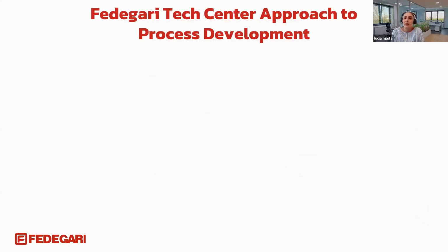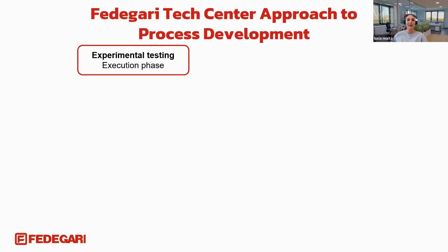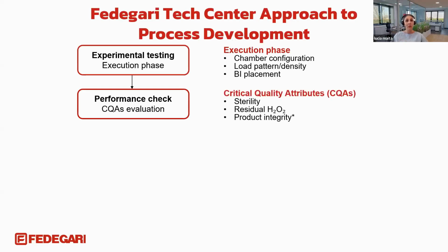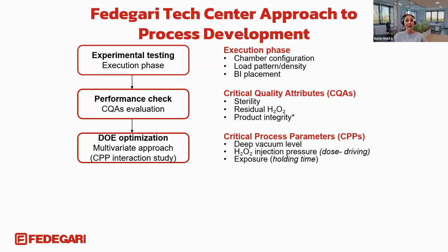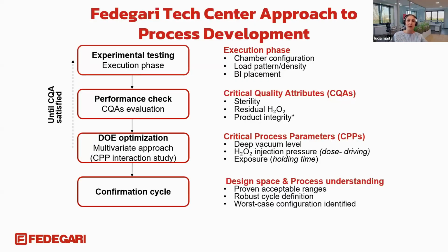At the Fedegari Tech Center, we develop sterilization processes using a structured and data-driven approach. The experimental design starts with defining the testing conditions, including the chamber load configuration, the loading pattern, and the biological indicator placement. After each sterilization cycle, the critical quality attributes such as sterility and residual H2O2 are evaluated, and based on these results, the critical process parameters are optimized until the required performance is achieved. The final cycle is then confirmed to demonstrate process robustness.